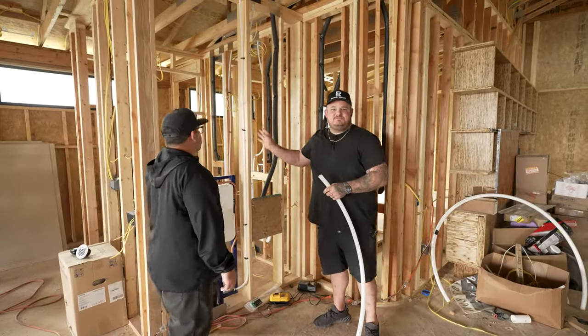In the kitchen — this is your ice maker box. This feeds the water to your refrigerator and it's a recessed box so we can put it in the wall and give it a nice look. We have to insulate this even though it's only cold water because it's on an exterior wall — on an exterior wall we have to insulate both hot and cold.